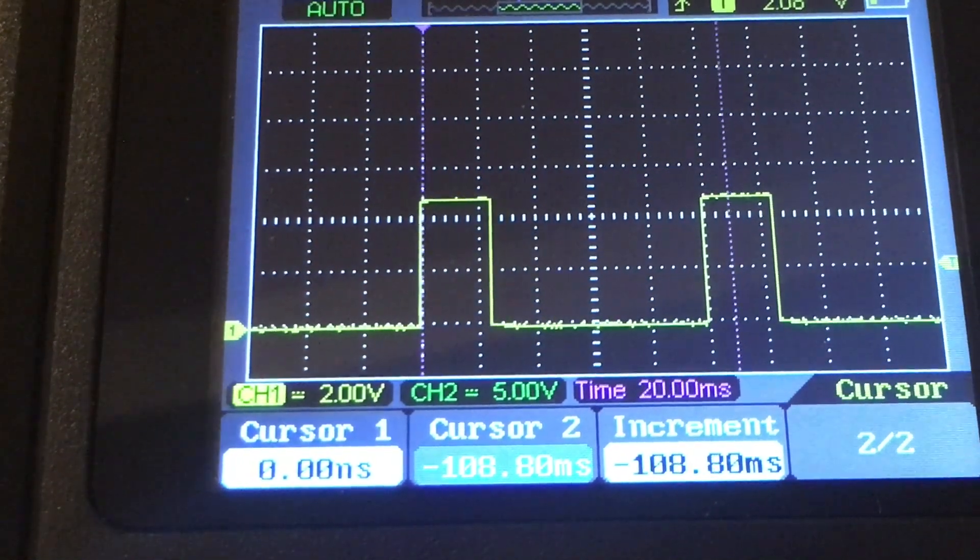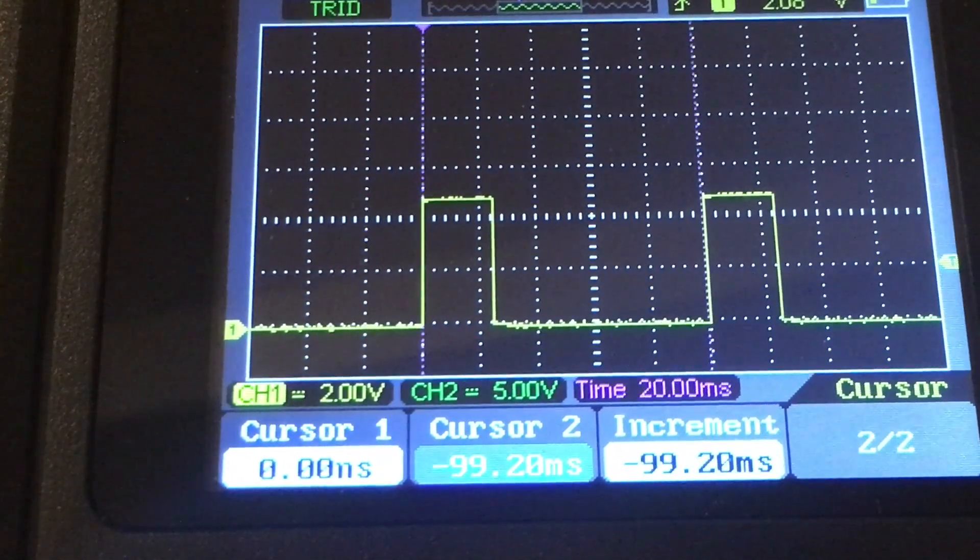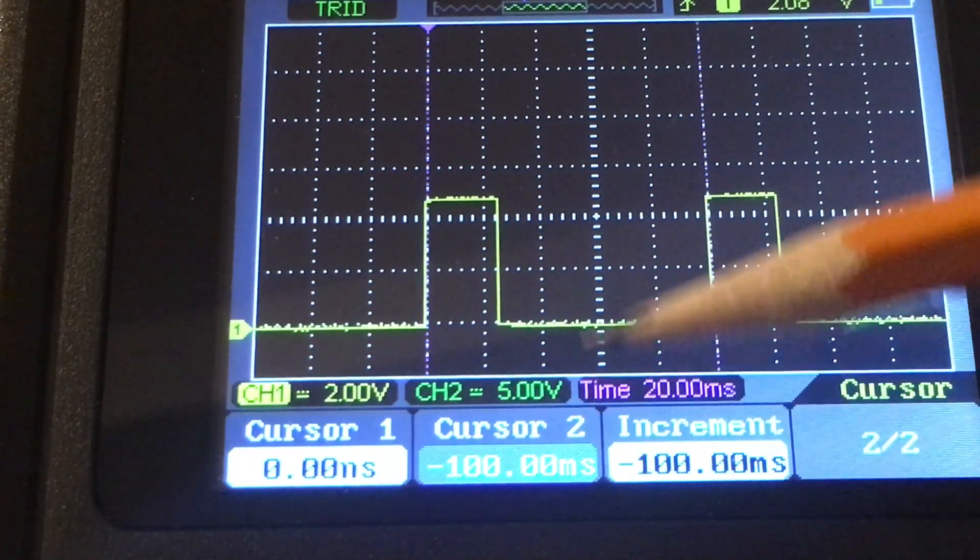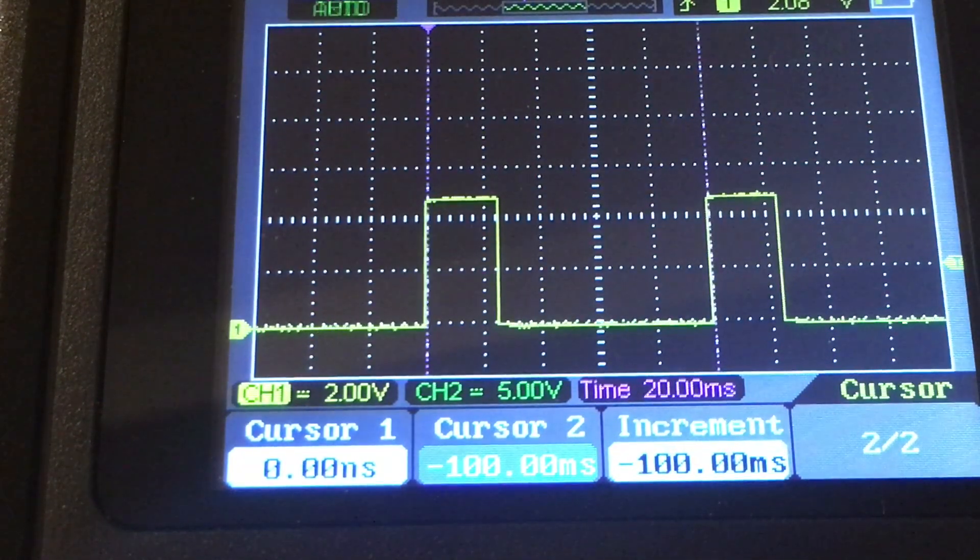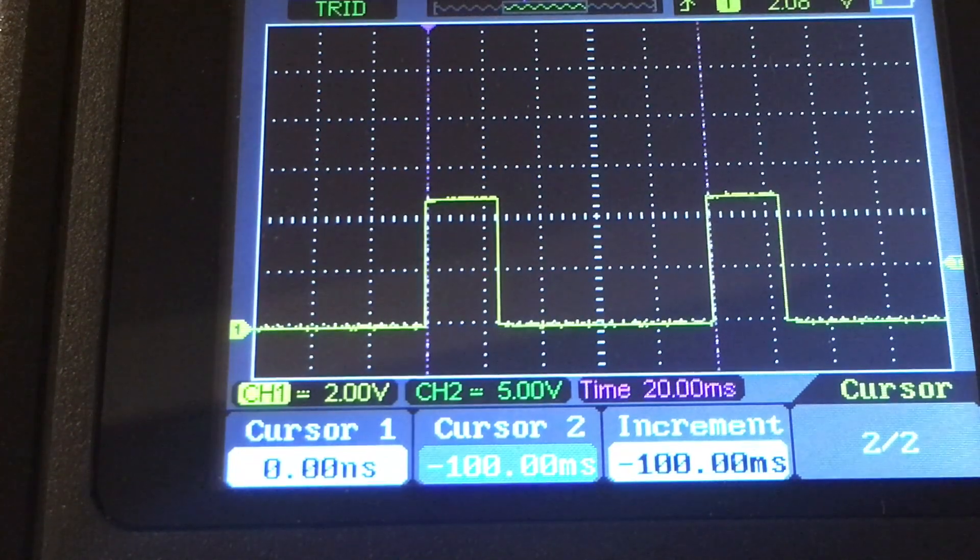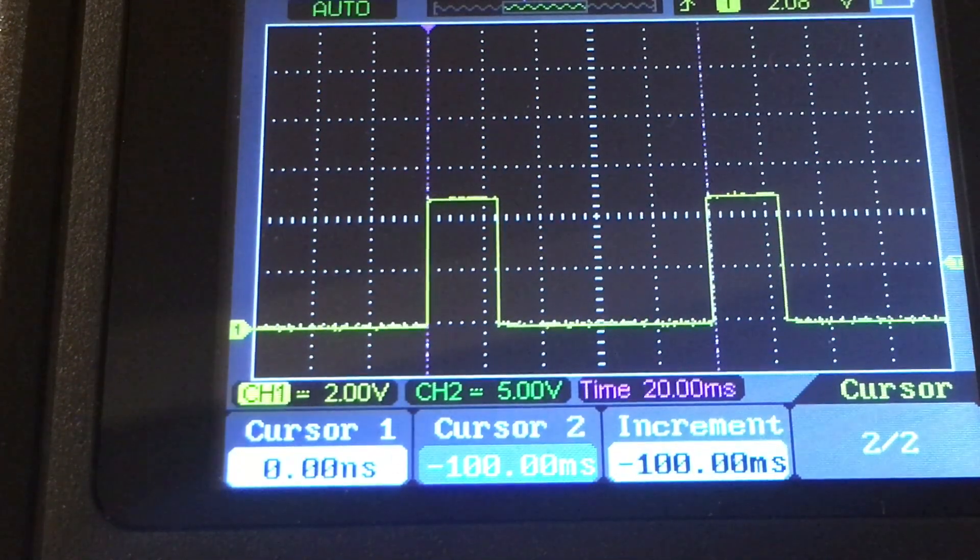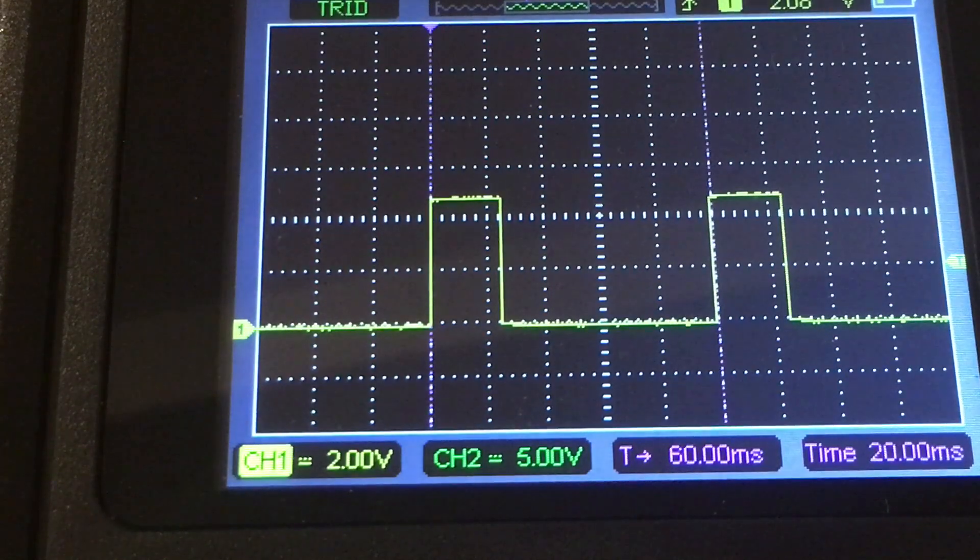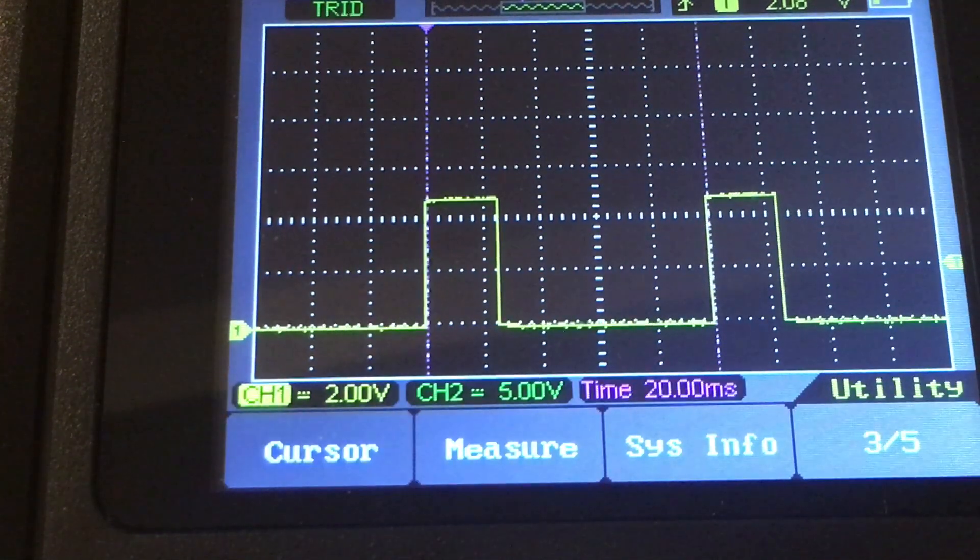Cursor two, I can move that to wherever we want it. So again, the absolute value from the reference and your value, this is 100 milliseconds in time from the reference point. Again, these two are reading the same because our first one is on the zero point, so that is the differential.